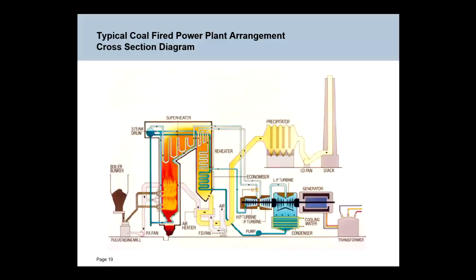Okay, so what do these things look like? This picture shows a cross-section of a typical coal unit, not quite to scale. What we have here is the main furnace with the coal burning. That coal comes from coal bunkers. It goes through a pulverizing mill where it's turned into something like a black flour. So it's ground to a very fine consistency and then blown by this primary air fan, which blows air through here, and is transported up to burners as a suspension in air. It then comes out of the burners and burns in flames that are 6 to 7 meters long. So these burners, we'll have a look at pictures of these in a minute. These are very large flamethrowers, okay?